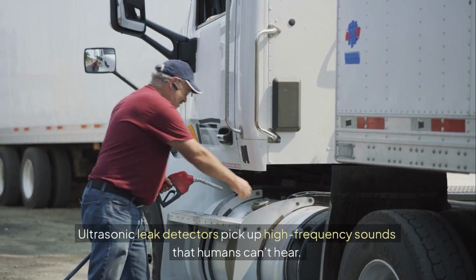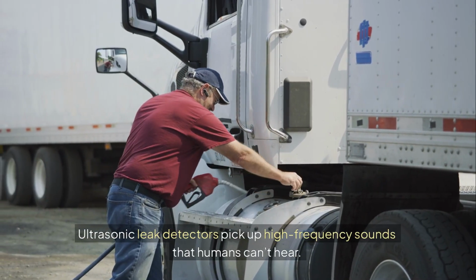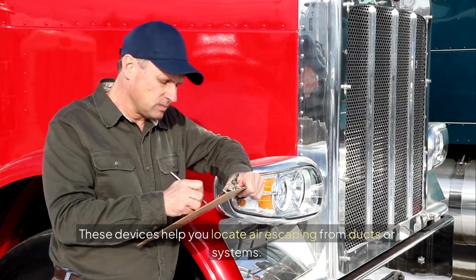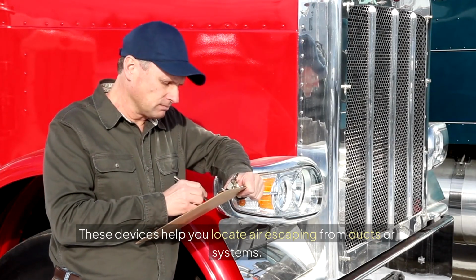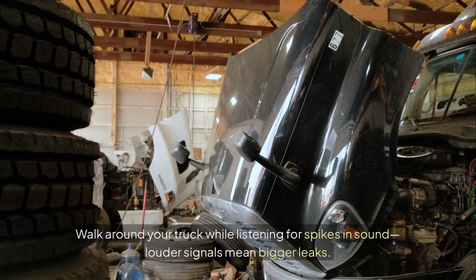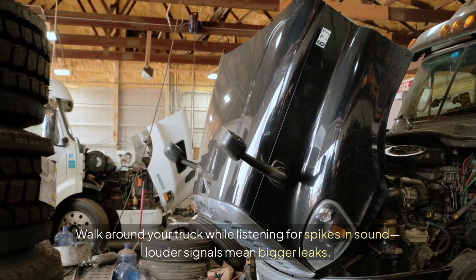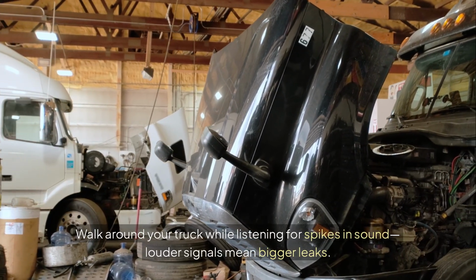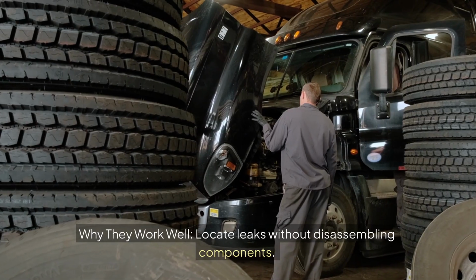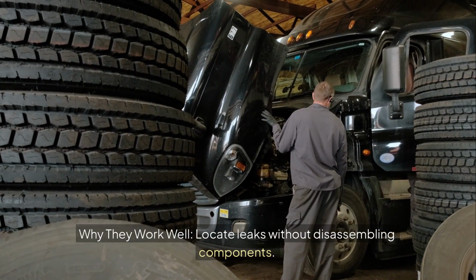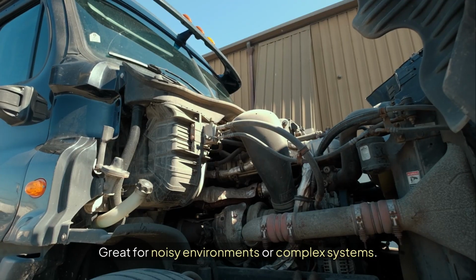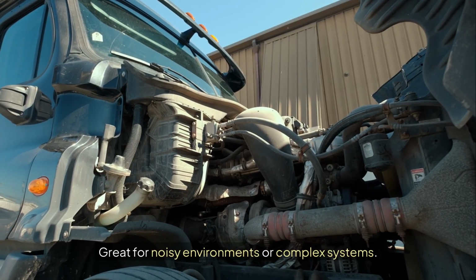Ultrasonic leak detectors. Ultrasonic leak detectors pick up high-frequency sounds that humans can't hear. These devices help you locate air escaping from ducts or systems. Walk around your truck while listening for spikes in sound. Louder signals mean bigger leaks. Why they work well: they locate leaks without disassembling components, and they're great for noisy environments or complex systems.